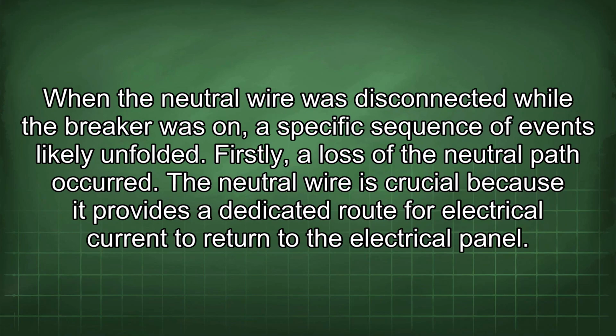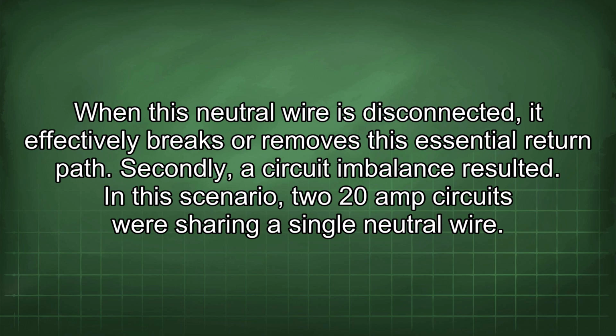When the neutral wire was disconnected while the breaker was on, a specific sequence of events likely unfolded. Firstly, a loss of the neutral path occurred. The neutral wire is crucial because it provides a dedicated route for electrical current to return to the electrical panel. When this neutral wire is disconnected, it effectively breaks or removes this essential return path.